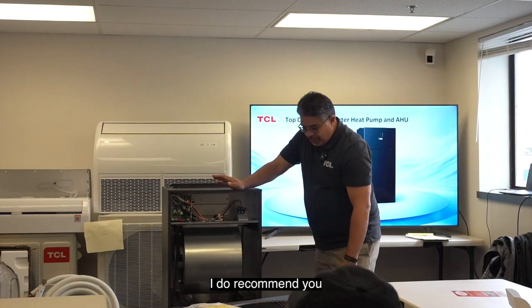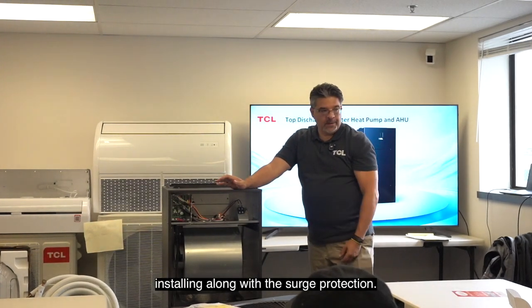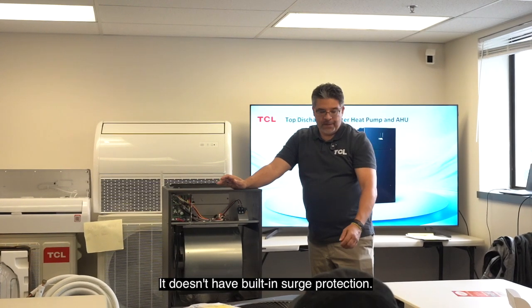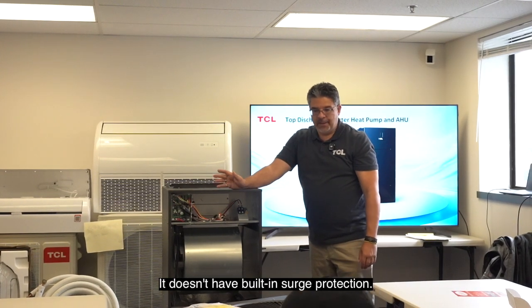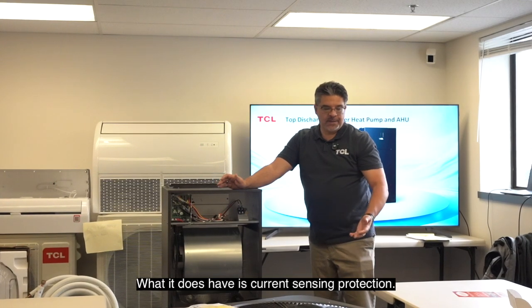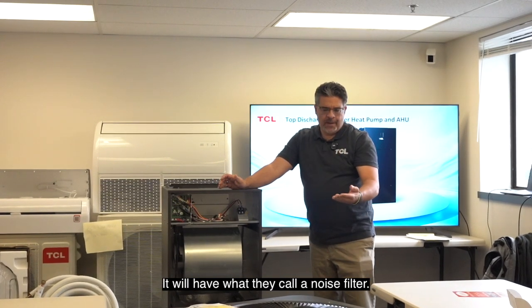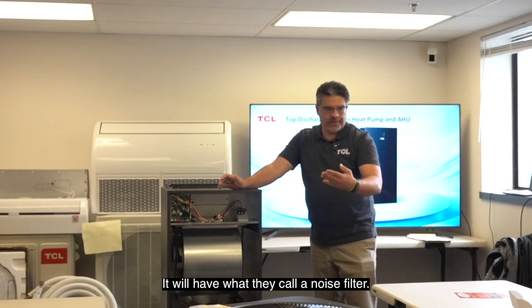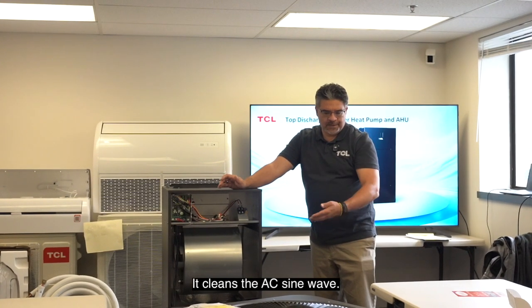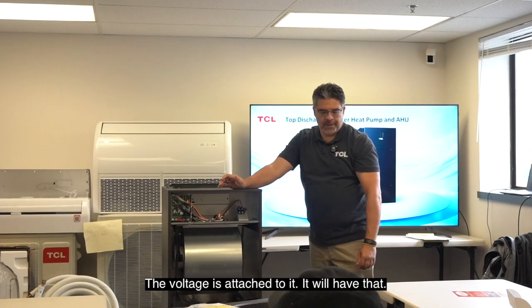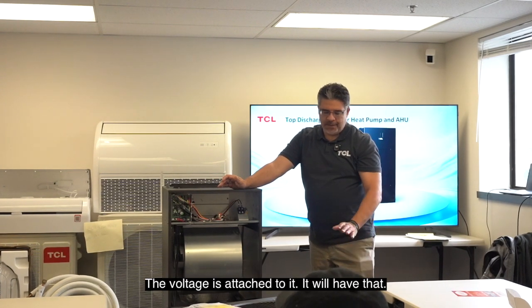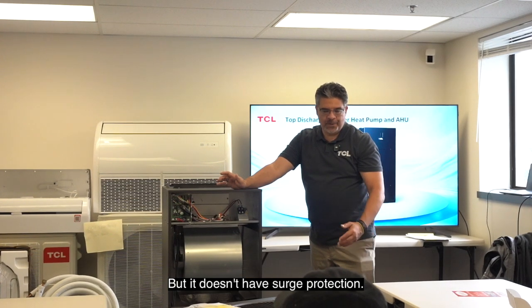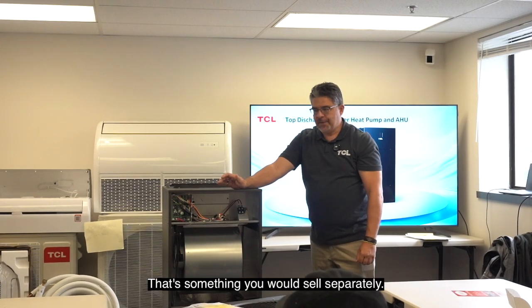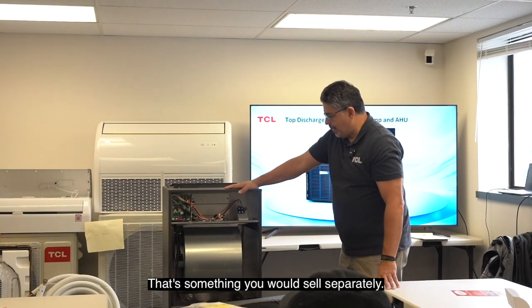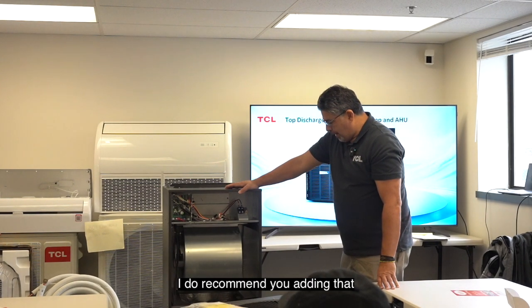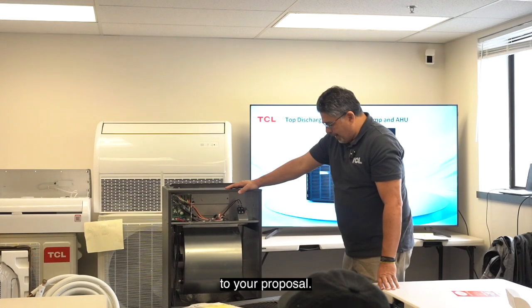I do recommend you installing it along with surge protection. It doesn't have built-in surge protection, but what it does have is current sensing protection, and it'll have what they call a noise filter, which cleans the AC sine wave, the voltage that is attached to it. It'll have that, but it doesn't have surge protection. So that's something you would sell separately, and because of the boards, I do recommend you adding that to your proposal.